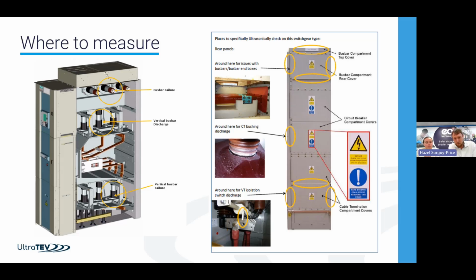We know, for instance, that surface activity can be particularly bad in some cases. Other issues have been internal discharge, through the bushing support, etc. That information is out there, and we've got a team here that can help advise you on that. The key bit is making sure that for the gear you have, you understand what the cross section looks like, where items are located internally, and the history and most likely causes of failure. We can then target your measurements as you go around, which will really improve the quality of your services. That's an area we can assist with.